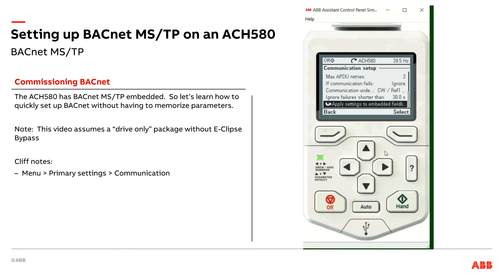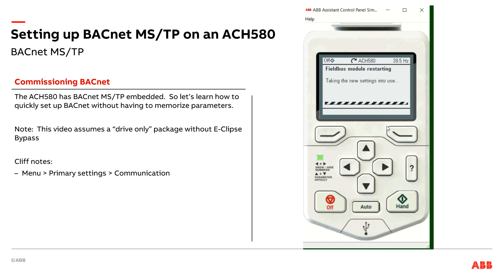Once you're done, with a lot of older products you have to cycle power to get the parameters saved into the drive. With the ACH 580, all I need to do is select the Apply Settings for the embedded fieldbus and it saves that information to memory within the drive. There is no need to cycle power.